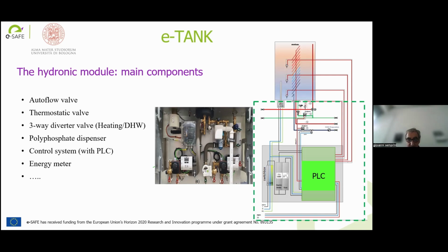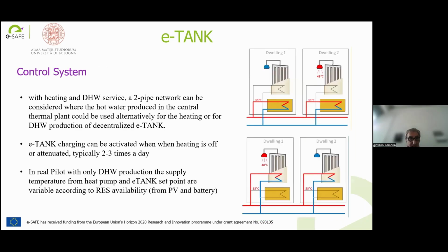With this PLC, it's possible to control and monitor the activities of the e-tank system. There is also a network connection by different protocols, but normally by the M-bus protocol. This connection enables communication and data transfer with the central control system of the building in order to manage all the e-tanks of the building. Special consideration about the control system: the control strategies must ensure the supply of the individual apartments with hot water. This is the main goal, obviously, to supply the correct values of temperature in each apartment.